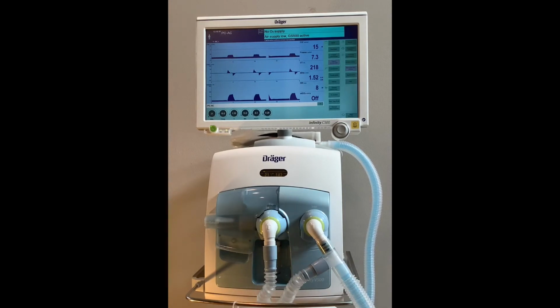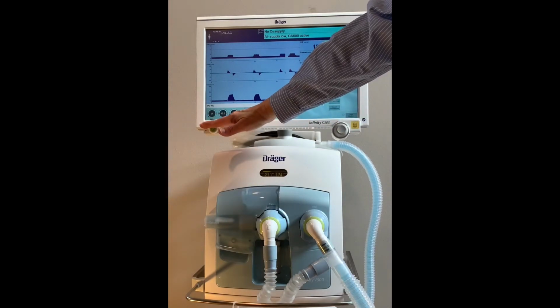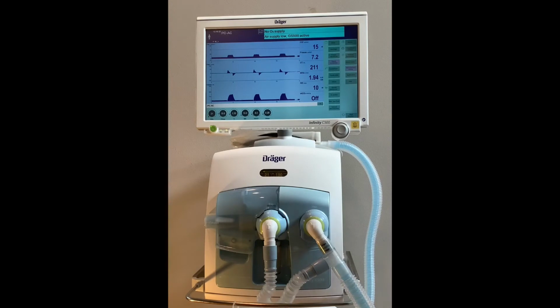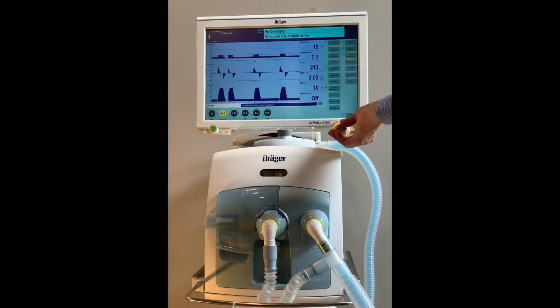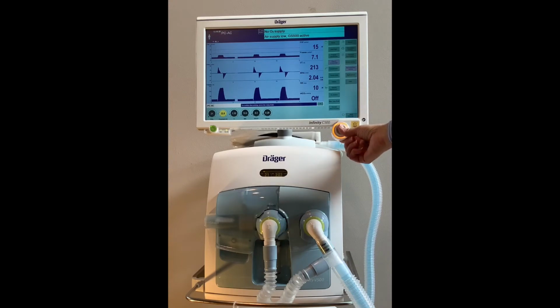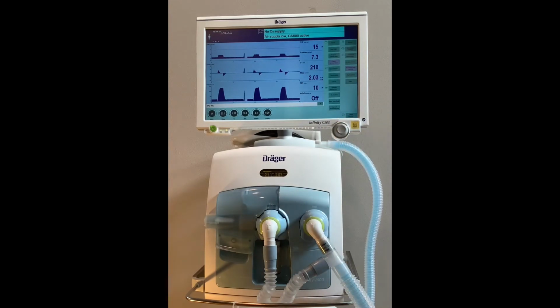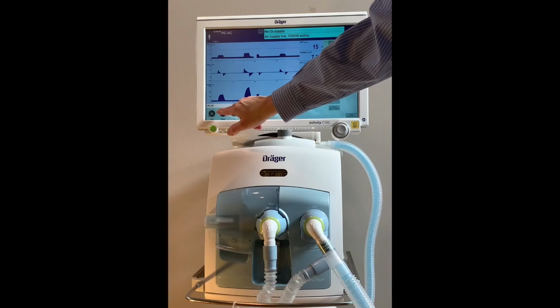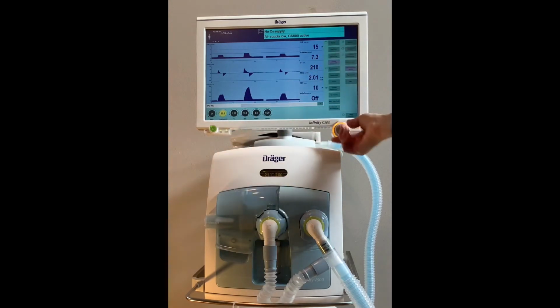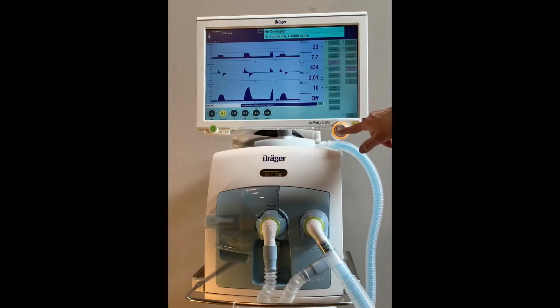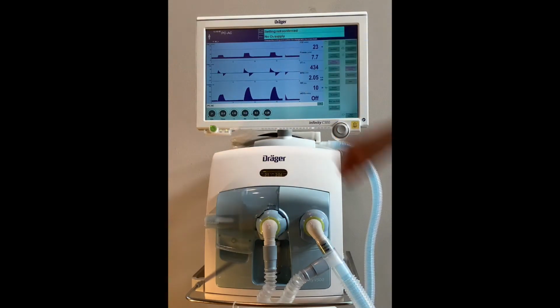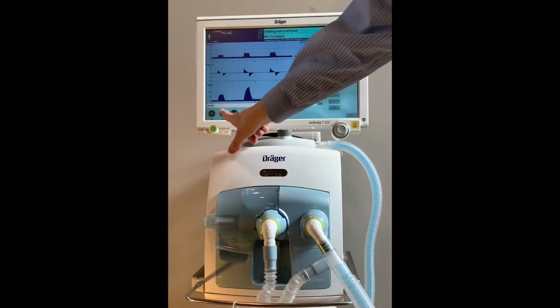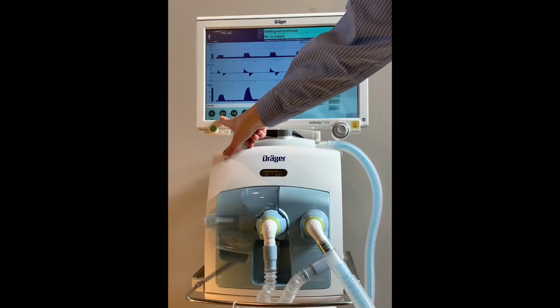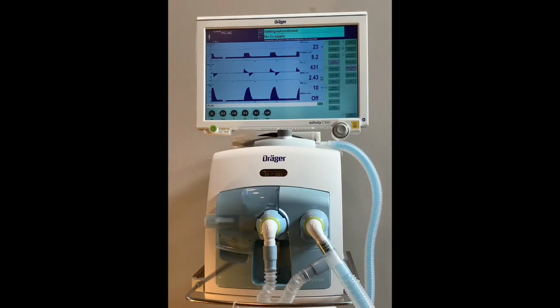The right-hand columns of the screen are for the shortcut tabs to take you to the functions that are used most often. To make a ventilator change to any of your basic ventilation parameters, we use the touch, turn, confirm method. Touch the button, use the rotary knob to dial in the desired value, and confirm. Touch, turn, confirm. If you do not confirm the value, the user will be prompted with a message that says setting not confirmed. Notice that the value has not changed and gone back to what was set originally.